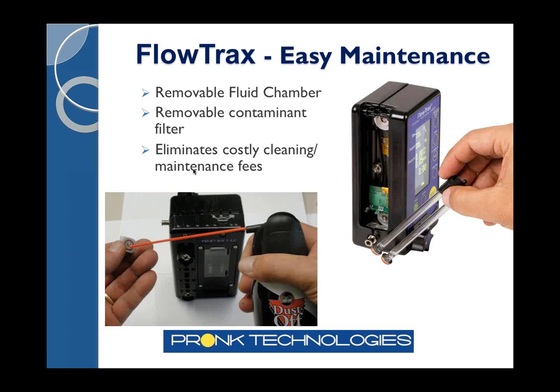Quickly, the Trax design requirements from day one were that we wanted it to be field serviceable so that you didn't have to send it back to us if, for example, you had any kind of fluid contamination take place. The fluid chamber is removable, and within 2 minutes you can pop that out, shown in the picture here, have that cleaned out with the cleaning solution we provide, and have it back up and running within a couple of minutes. There's also a filter that can pop out of the Trax, that you can take out and clean very quickly in case there's any contaminants in there.